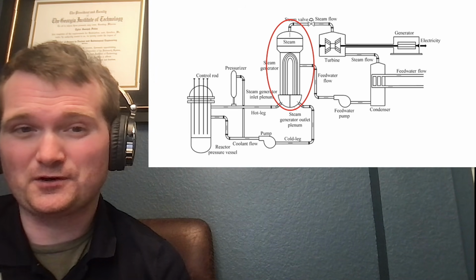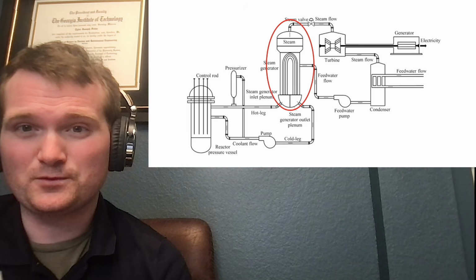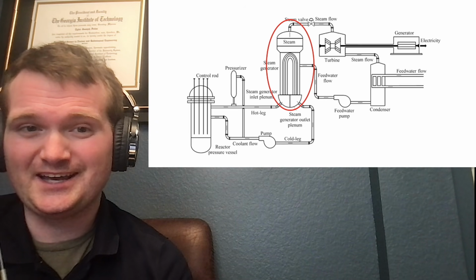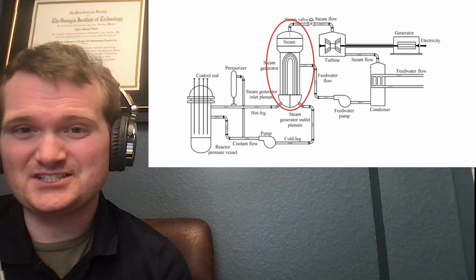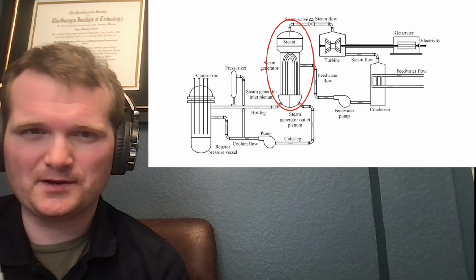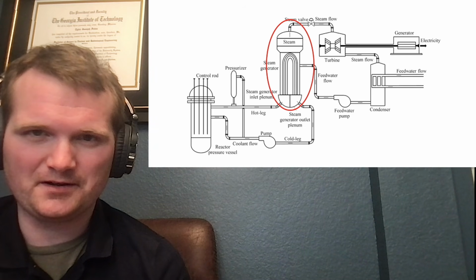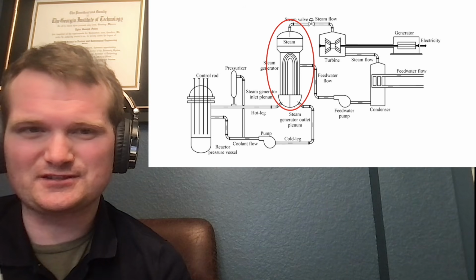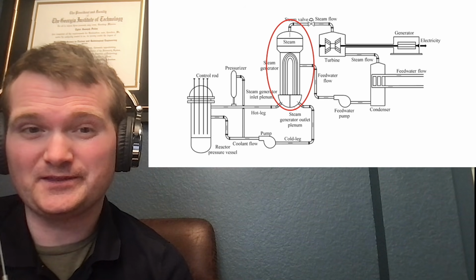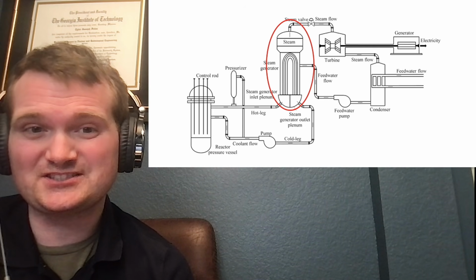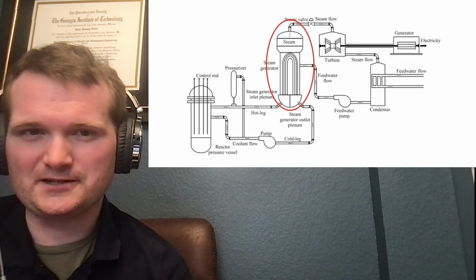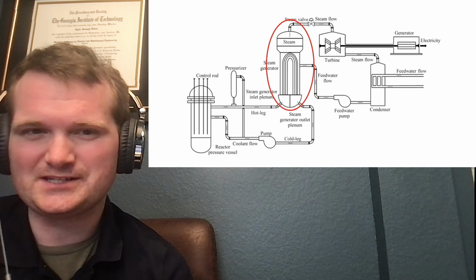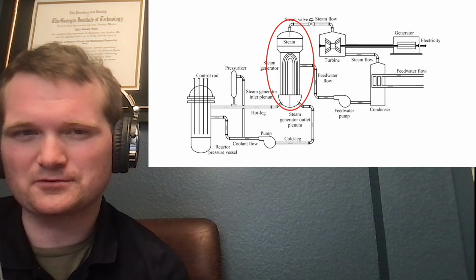You also have feed water heaters in these loops where you take steam from the turbine and put it in stages to heat it up further so it can be ready to go into the steam generator. It's just a form of preheating. It's no different than preheating your oven makes cooking a lot more efficient than if you put your chicken in the oven and you had to wait for it to preheat to 400 degrees or whatever.